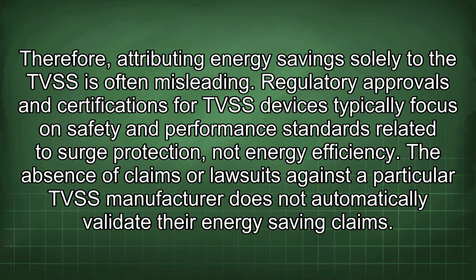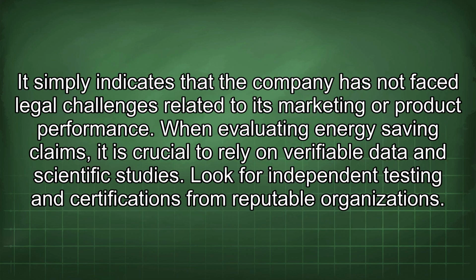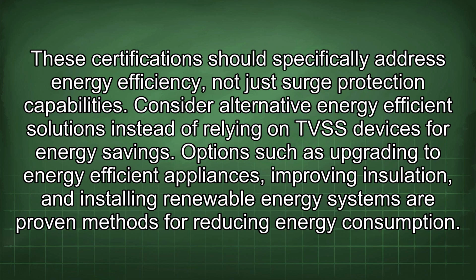Regulatory approvals and certifications for TVSS devices typically focus on safety and performance standards related to surge protection, not energy efficiency. The absence of claims or lawsuits against a particular TVSS manufacturer does not automatically validate their energy-saving claims. It simply indicates that the company has not faced legal challenges related to its marketing or product performance. When evaluating energy-saving claims, it is crucial to rely on verifiable data and scientific studies. Look for independent testing and certifications from reputable organizations. These certifications should specifically address energy efficiency, not just surge protection capabilities.